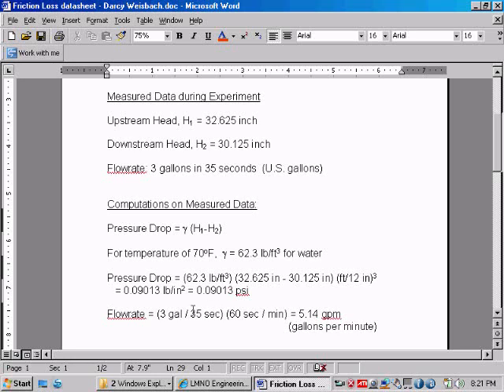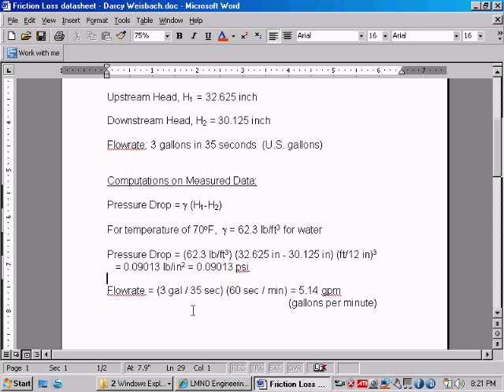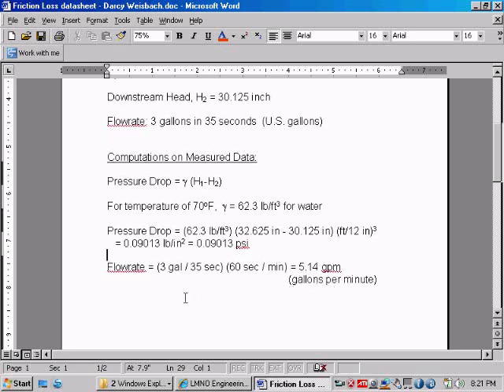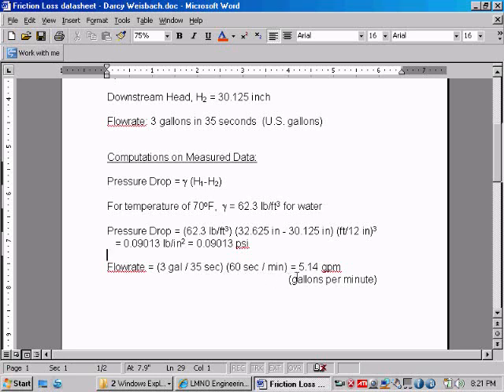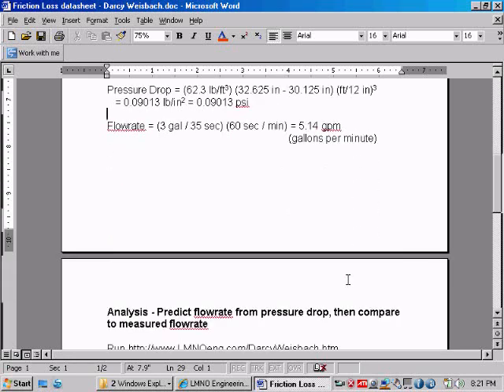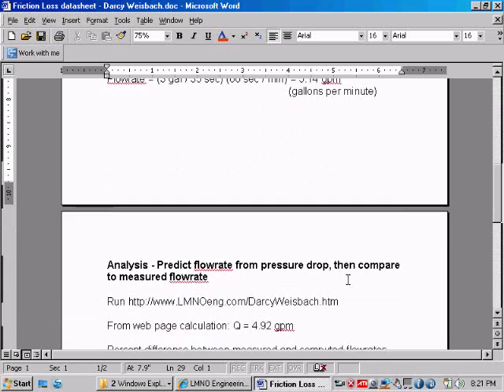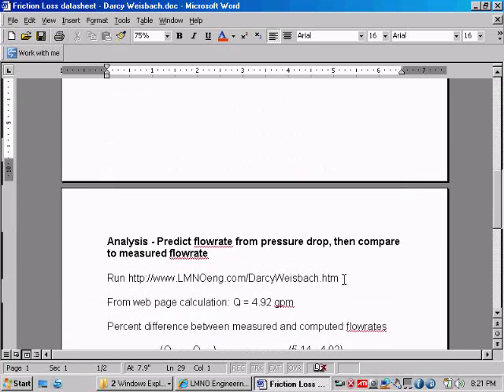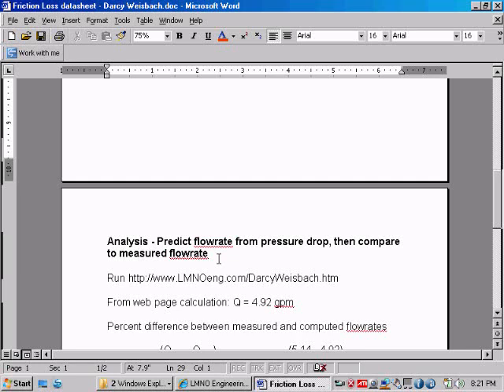The flow rate can be converted to gallons per minute by taking the three gallons that were measured in a 35 second period times 60 seconds per minute unit conversion gives us 5.14 gallons per minute, or GPM, which is U.S. gallons per minute. So we are then going to predict the flow rate from the pressure drop using a calculation on our website and then compare that predicted flow rate with the flow rate measured from the experiment.